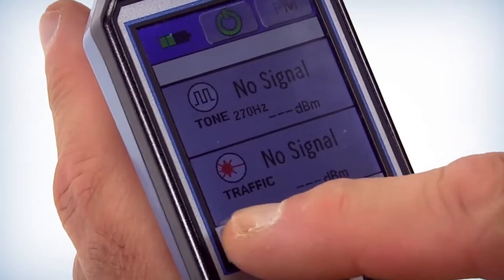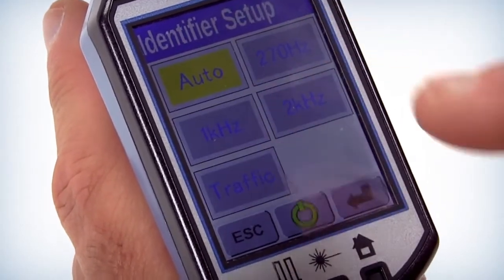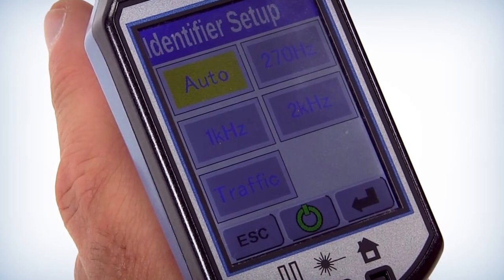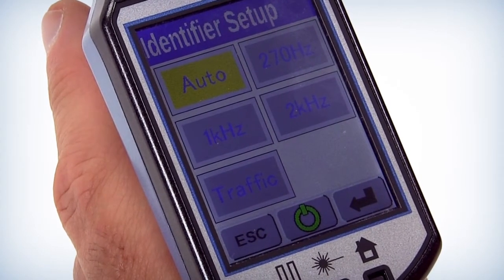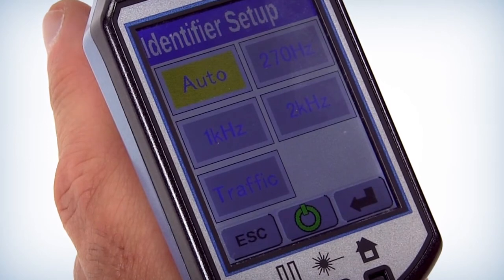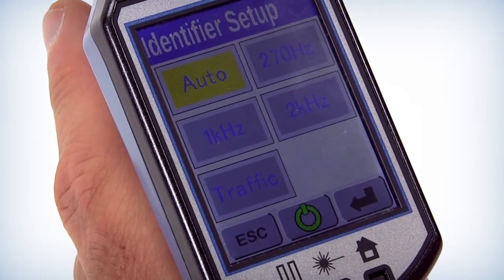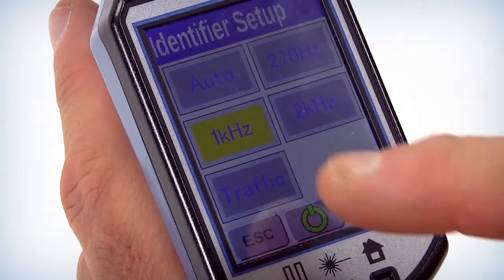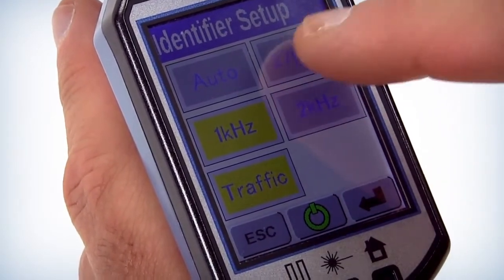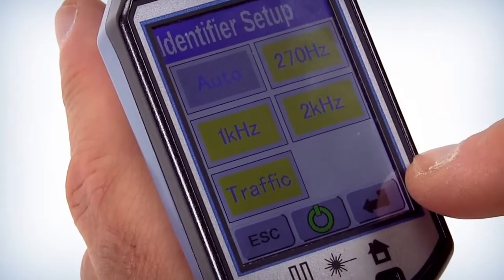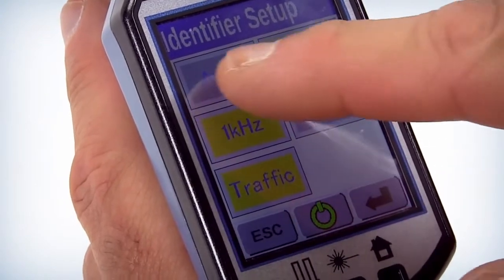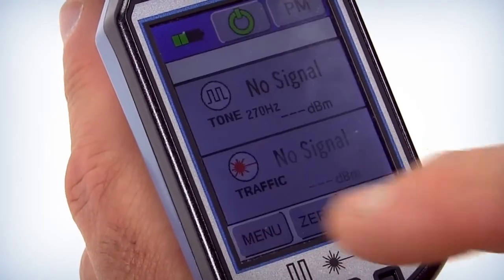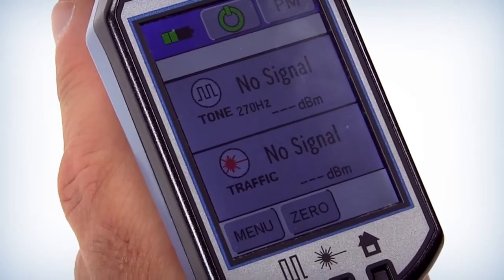Next, modify the Identifier Mode. Here you can select the tone you will be trying to detect. If you select Auto, the device will automatically detect any tone or traffic which is present on the fiber. Save your selection by pressing the Return arrow at the bottom right of the screen. To exit the screen without saving your selection, you can return to the menu screen by selecting the Escape button in the lower left corner of the screen.